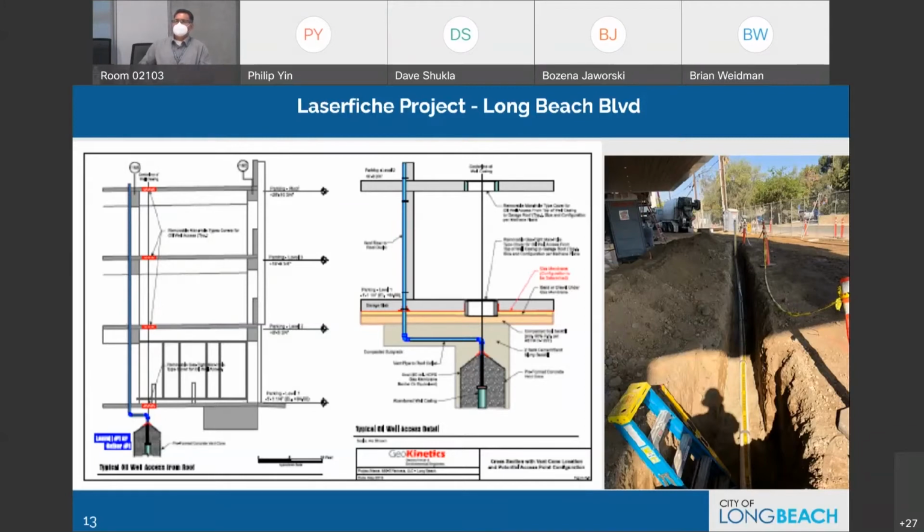Now, following the prescriptive method that the city just approved under 18.78, from the vent cone outlet, a Schedule 40, normally Schedule 40 PVC pipe, or ABS pipe, is connected and in this case is taken off horizontally to where it's going to be terminated at the location of a flagpole.